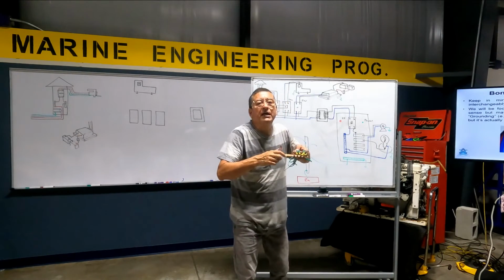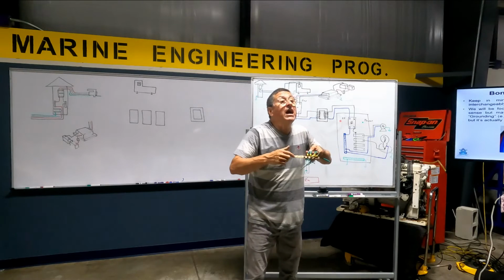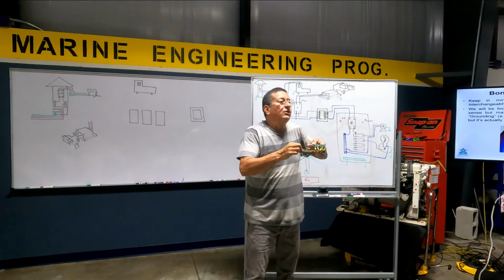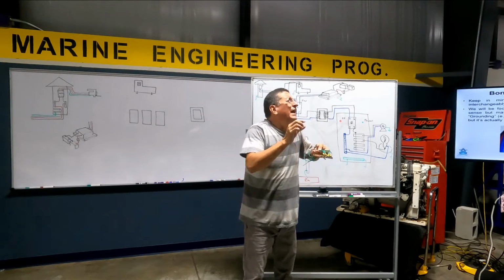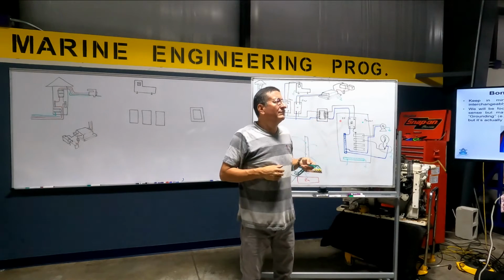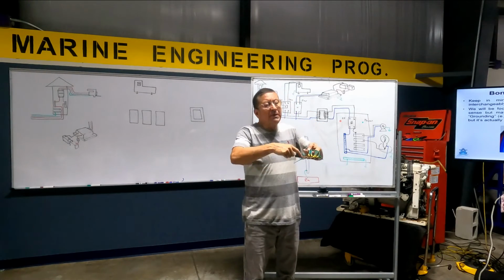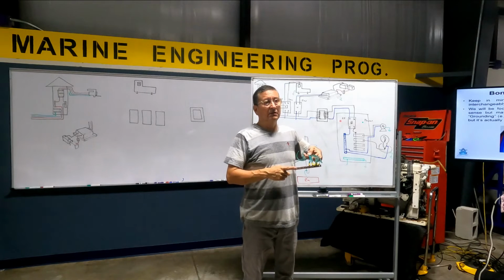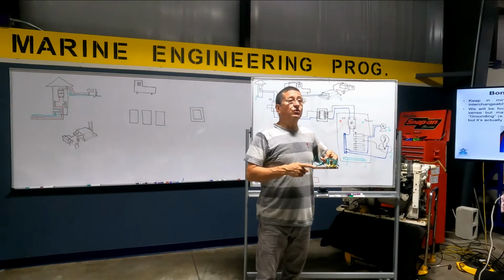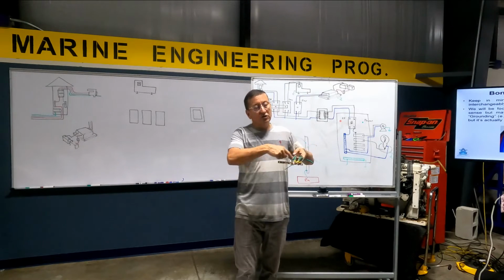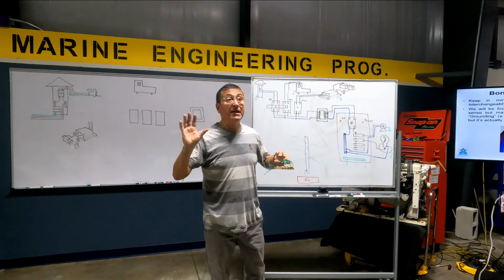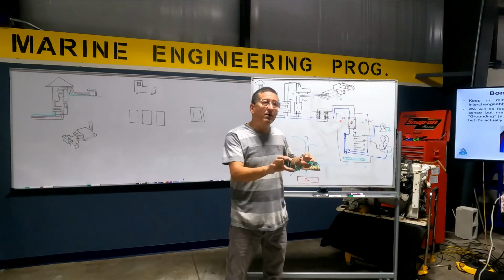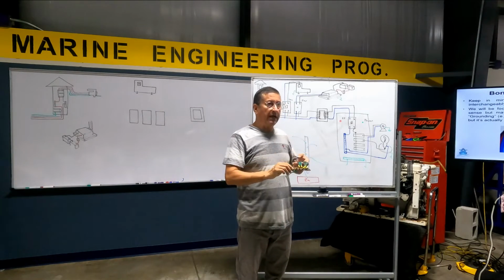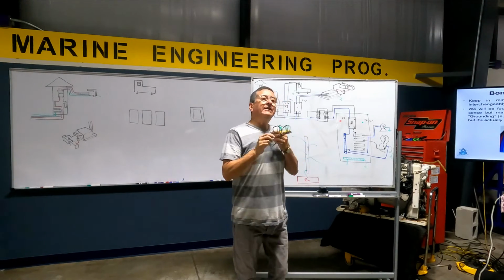How much voltage, how many amps are flowing here in normal conditions? Zero? Yeah, 0.00 something, very little. Is 5 amps normal here? No. 3 amps? No, that's too much. I have 1.5 amps constantly here — no, papi, that's a big leak of current. You need to identify where the leak is. Okay guys, pay attention.